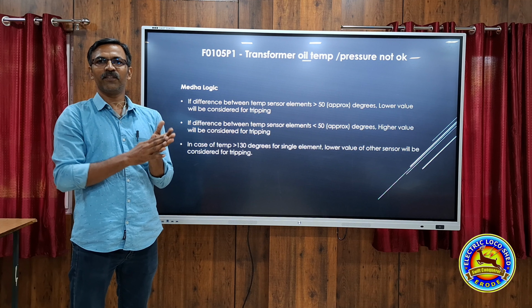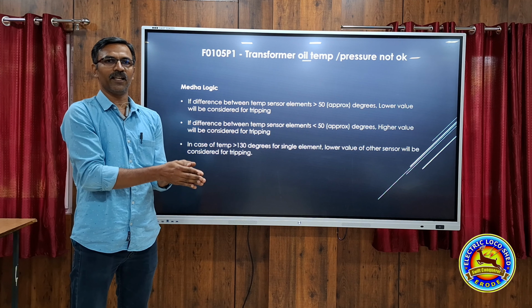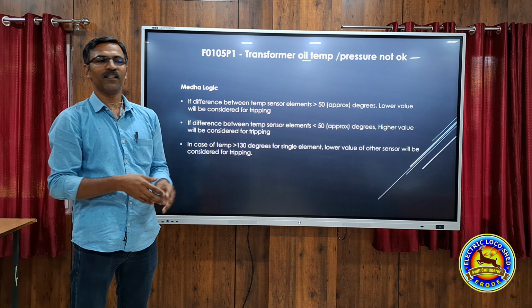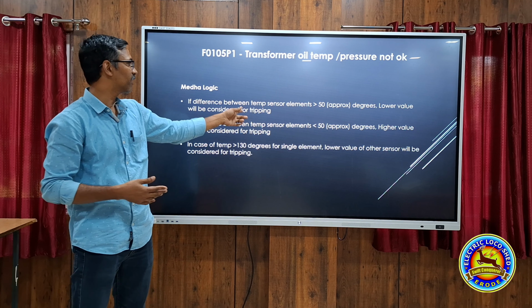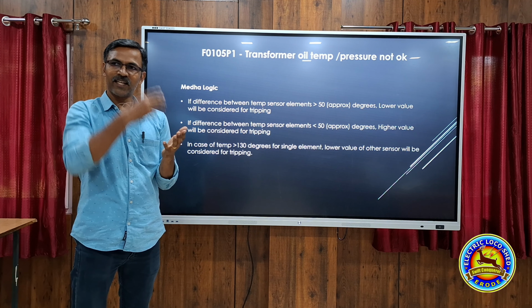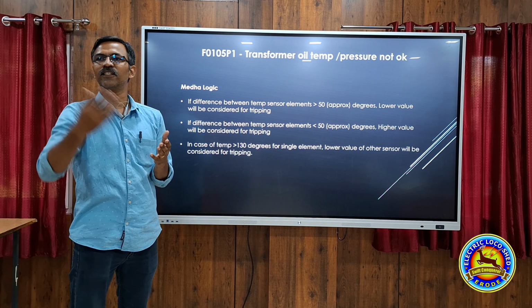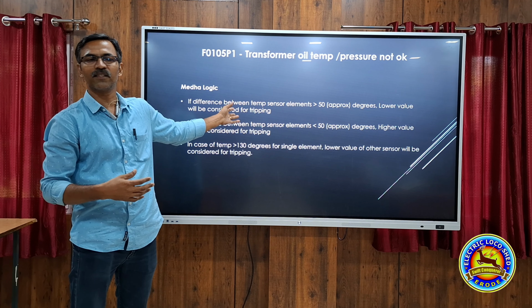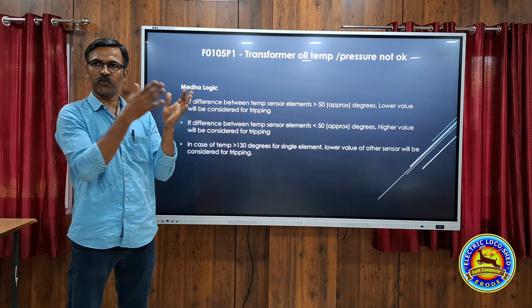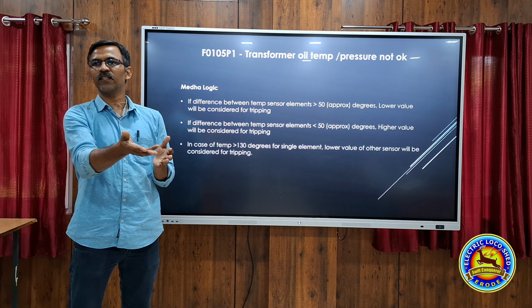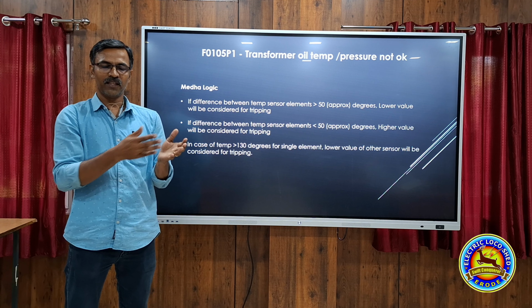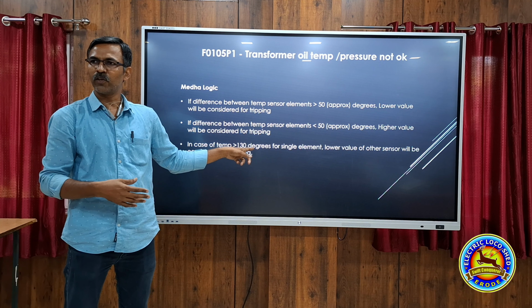That is, if one sensor is showing 30 and the other sensor is showing 90, then it will not trip. It will take the lower value because between 30 and 90 there is a difference of 60 degrees. So the lower value will be considered. The DJ will not trip. But in case the difference is less than 50, then the higher value will be taken. For example, if one sensor is showing 40 and the other sensor is showing 85, the difference is 45 degrees only. So it will take the higher value for tripping the loco. In that case, the DJ will trip.